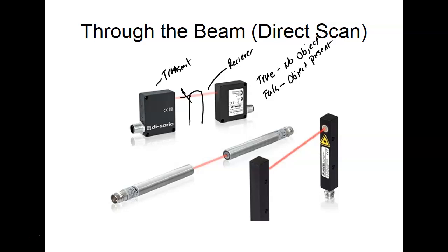So the biggest problem we have with these, of course, is alignment. Your transmitter and your receiver have to be aligned real well, right? You understand if they get off a little bit, that gives you a problem. So something comes on and knocks your little mount off there. So usually they're mounted on some type of mount if you move around. Very reliable, and they have a pretty good distance range too.